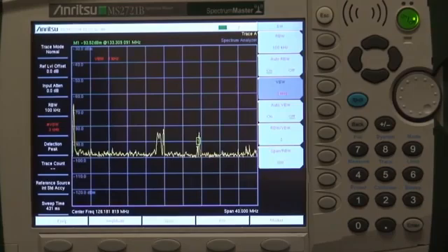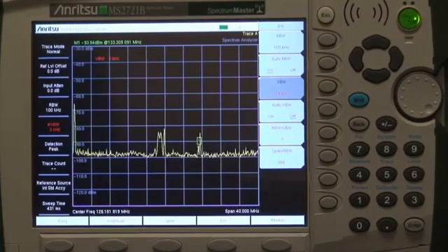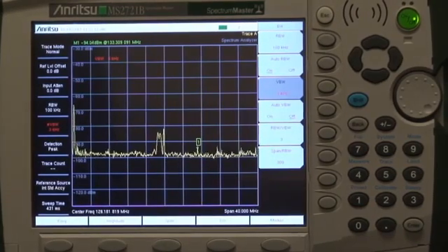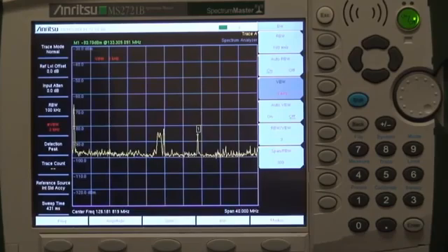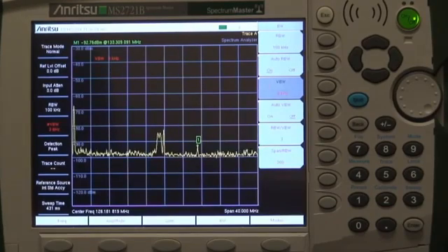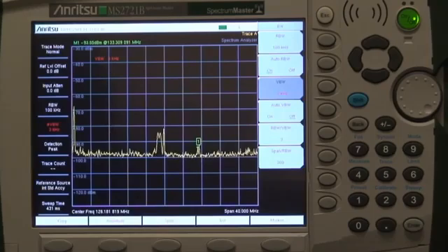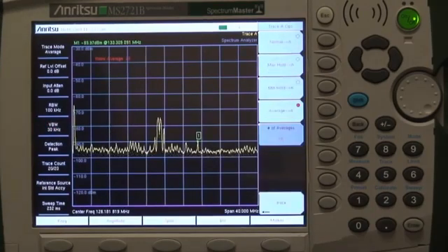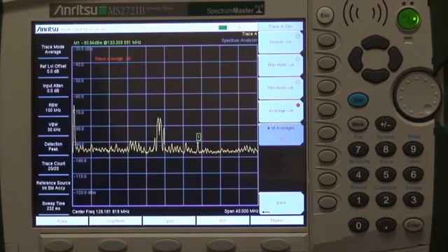This measurement was made using a narrow video bandwidth to clean up noise variations on the trace. Notice that the small signal at the marker position is easily seen with the narrow video bandwidth, and the sweep takes about 431 milliseconds. You can get just about the same results by averaging 20 traces, but it takes longer to get the results — about 2.3 seconds.